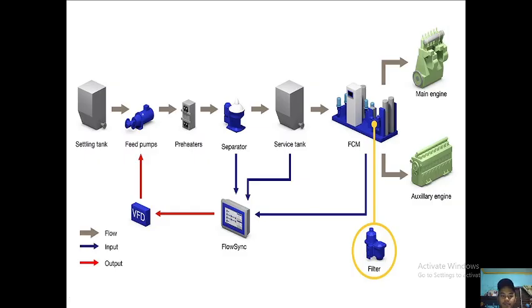So this is the setup. From the settling tank, the fuel is delivered to the separator via the feed pump, going to a preheater to heat up the fuel before purifying it. After purification, it will go to the service tank. And then from the service tank, it will go to the FCM or fuel conditioning module and to the engine. The FCM, the service tank, and the separator are controlled by a FlowSync and also by a VFD. So this is an automation.